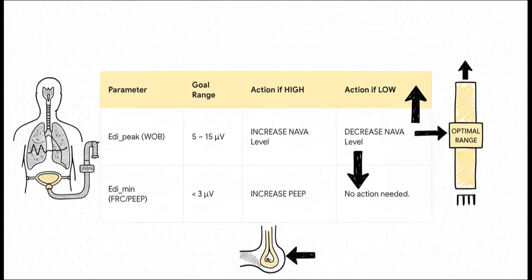NAVA is not a set-it-and-forget-it mode. It's a dynamic process, all about titration. Your goal is to keep the patient's work of breathing, which is represented by the Edi peak, in that sweet spot, that optimal range of 5 to 15. If it's too high, the patient's working too hard. You need to increase the NAVA level. If it's too low, they might be over-supported, so you'll want to decrease the NAVA level.